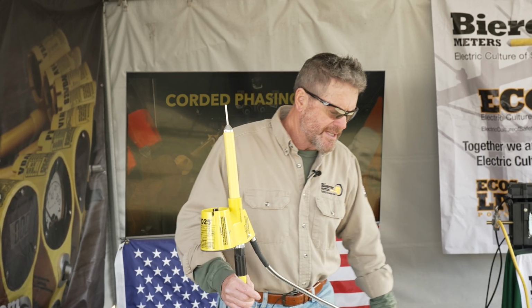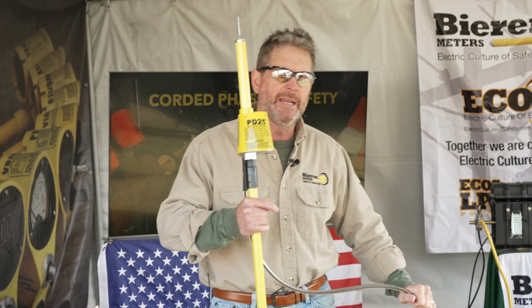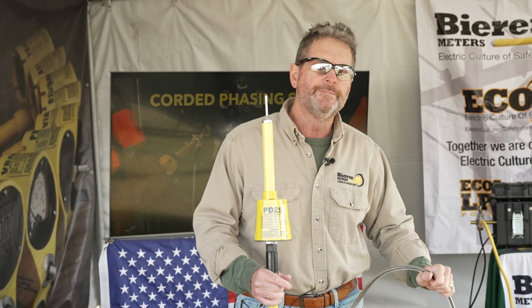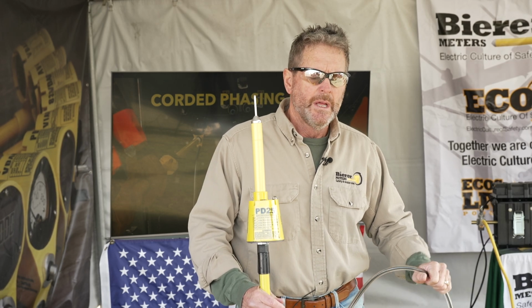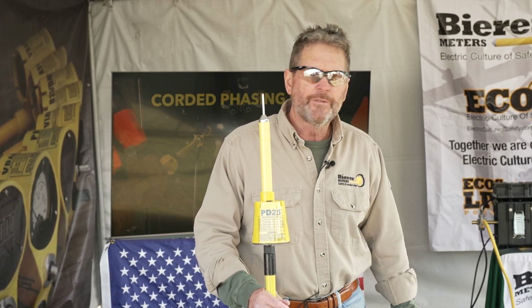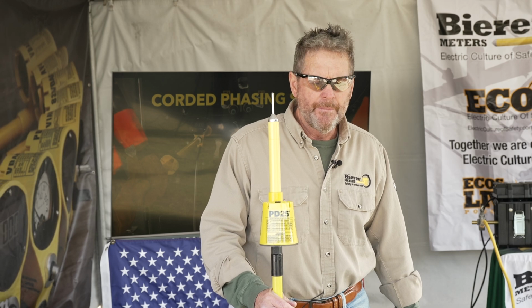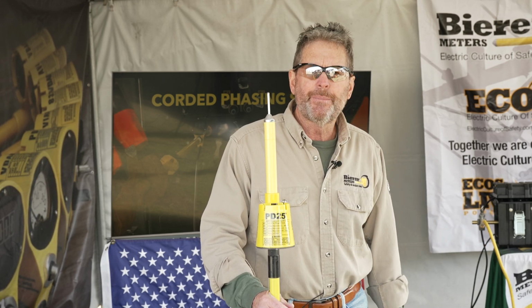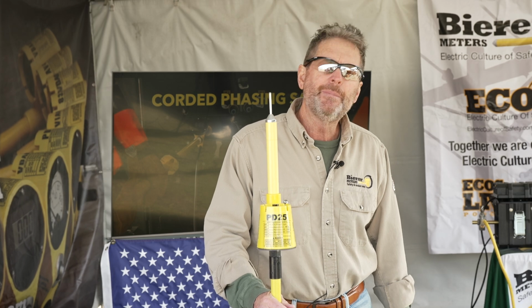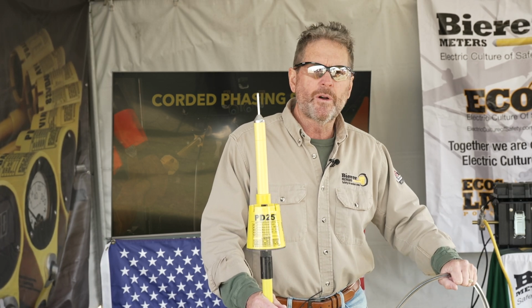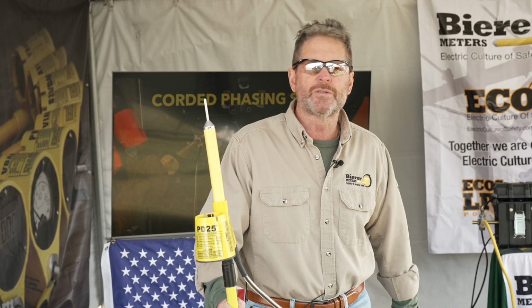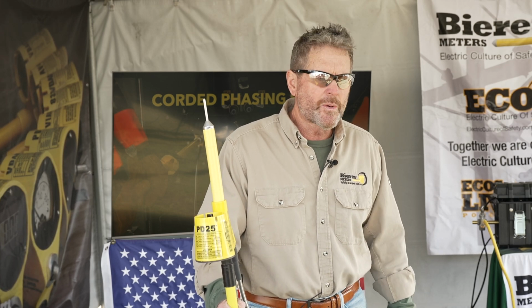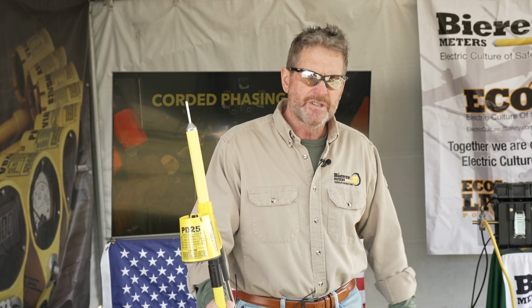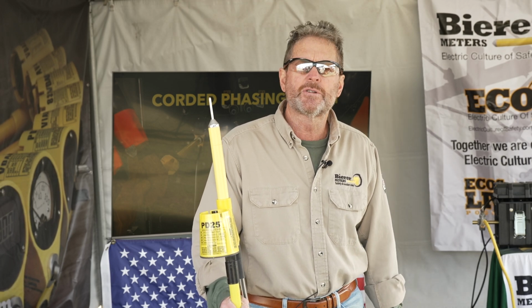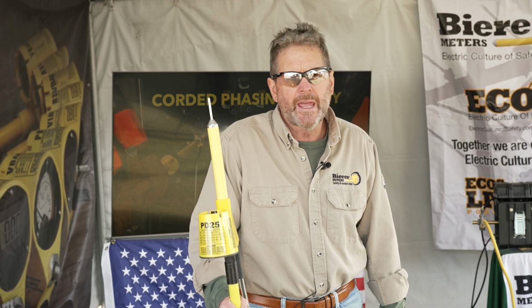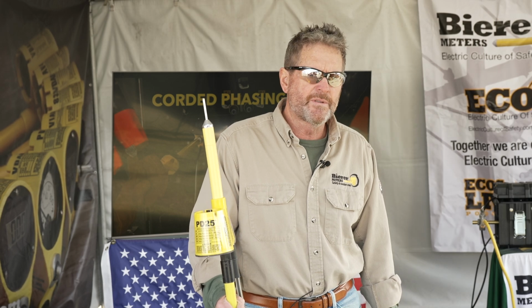When you use this tool, the PD25 or PD50, you can have the cord on the ground while you're phasing across a box - it can be laying on the box, it's safe. Maybe you're in the bucket truck and the cord inadvertently comes in contact with another phase or the neutral while you're using it - it's okay, it'll be fine. Just make a little adjustment, get it off that neutral, get it off that other phase. It's okay.